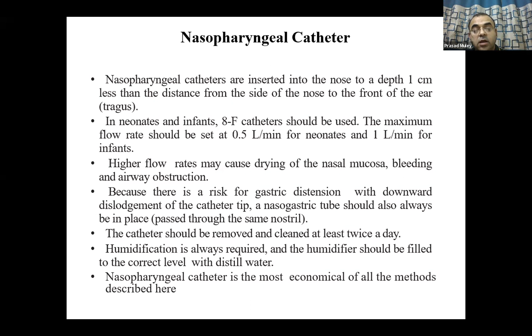Because here we are putting it more towards the pharynx side, there's always a chance that it may get dislodged into the esophagus, or some amount of air may go into the stomach. So gastric distension possibility is always there. So we have to always keep a nasogastric tube along with it, and the catheter should be removed and cleaned at least twice daily, because this catheter has more tendency to get obstructed over a period of time. Humidification is always required, and the humidifier should be filled to the correct level with distilled water, as we always do with the rest of the devices.